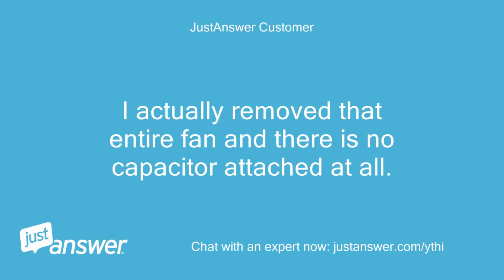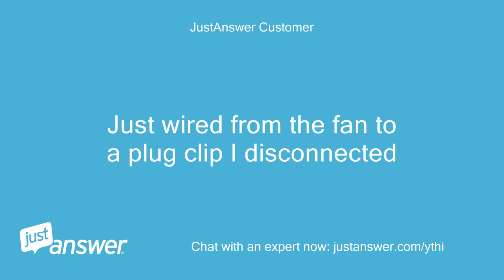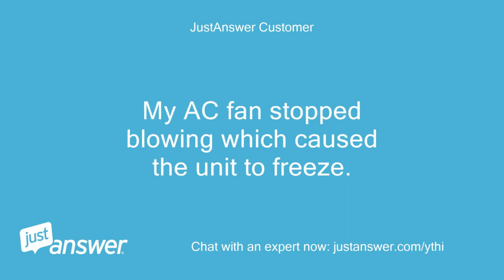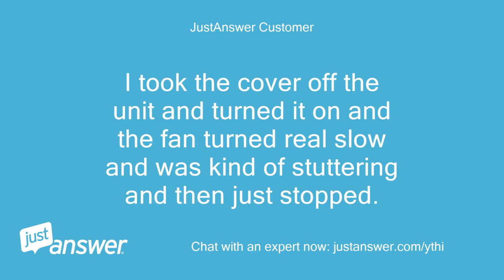I actually removed that entire fan and there is no capacitor attached at all, just wires from the fan to a plug clip I disconnected. My AC fan stopped blowing, which caused the unit to freeze. I took the cover off the unit and turned it on, and the fan turned real slow and was kind of stuttering, then just stopped.